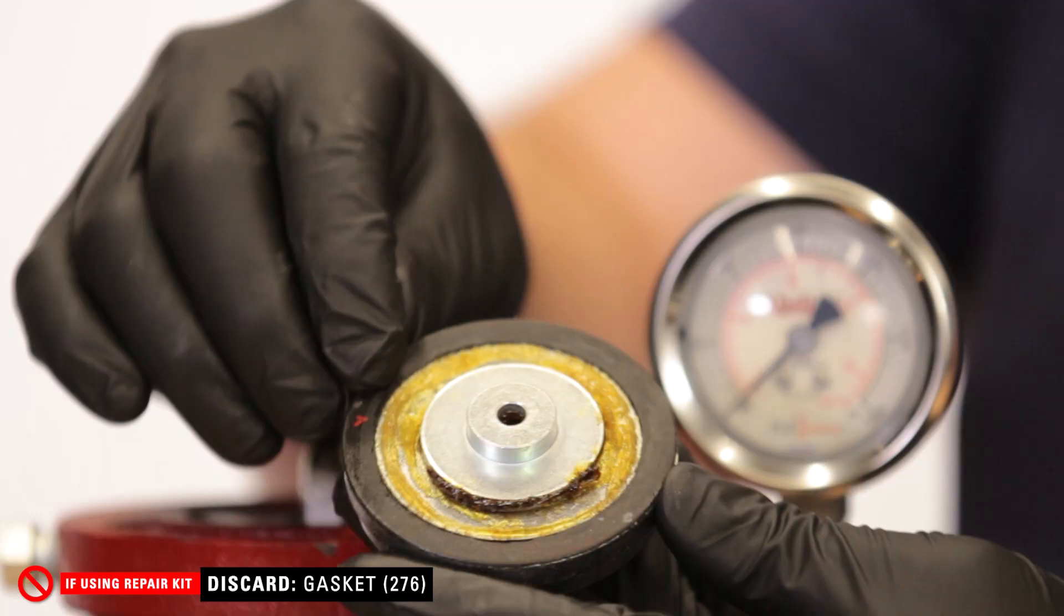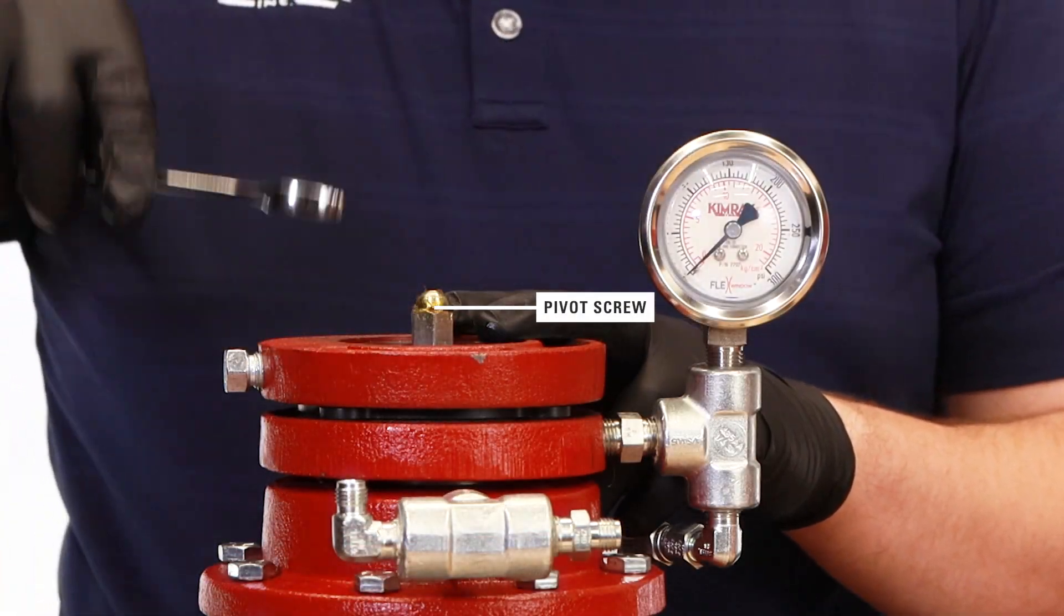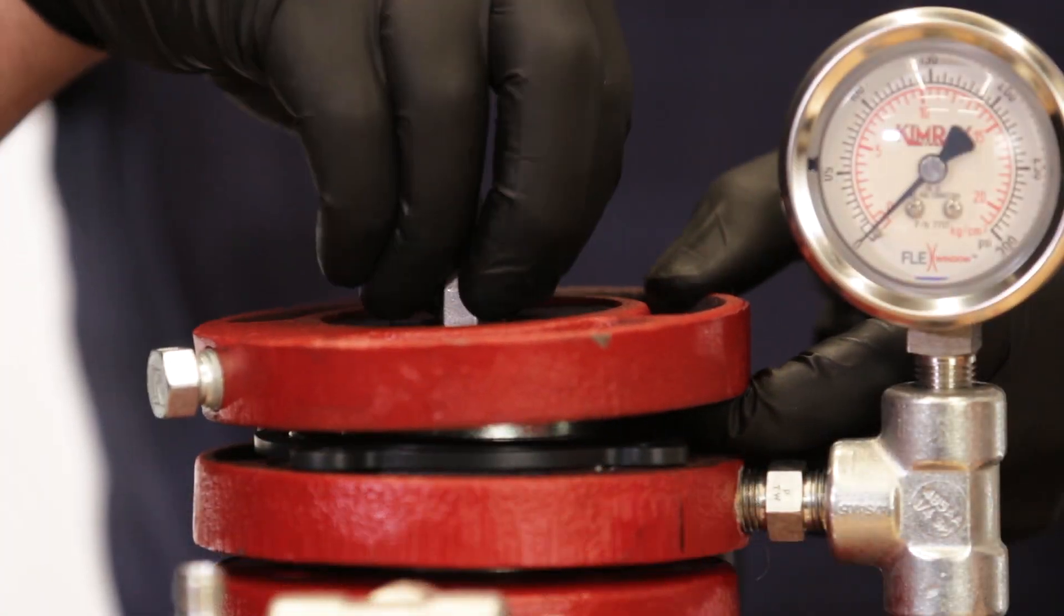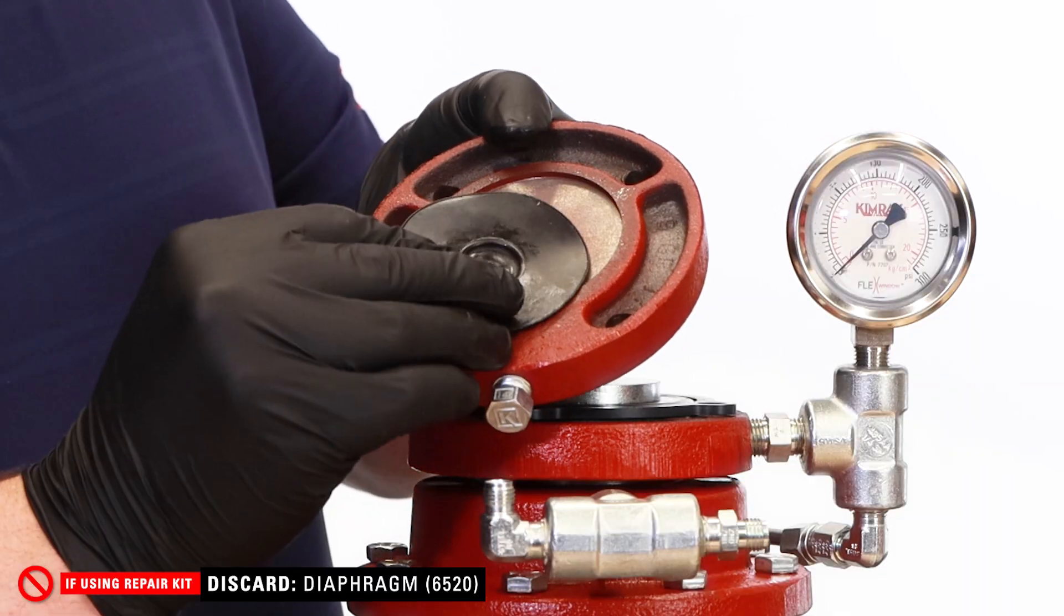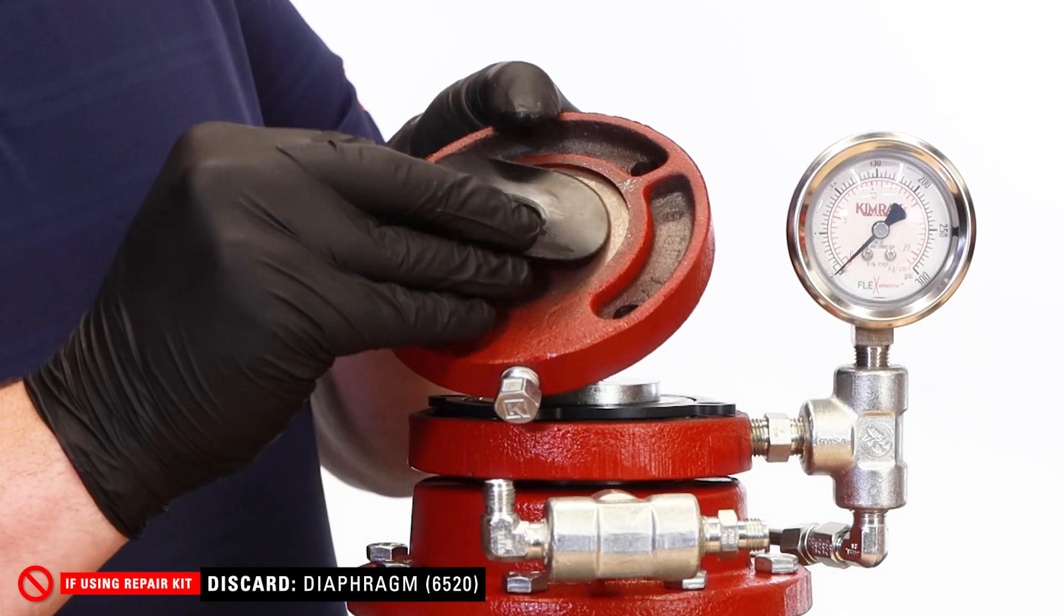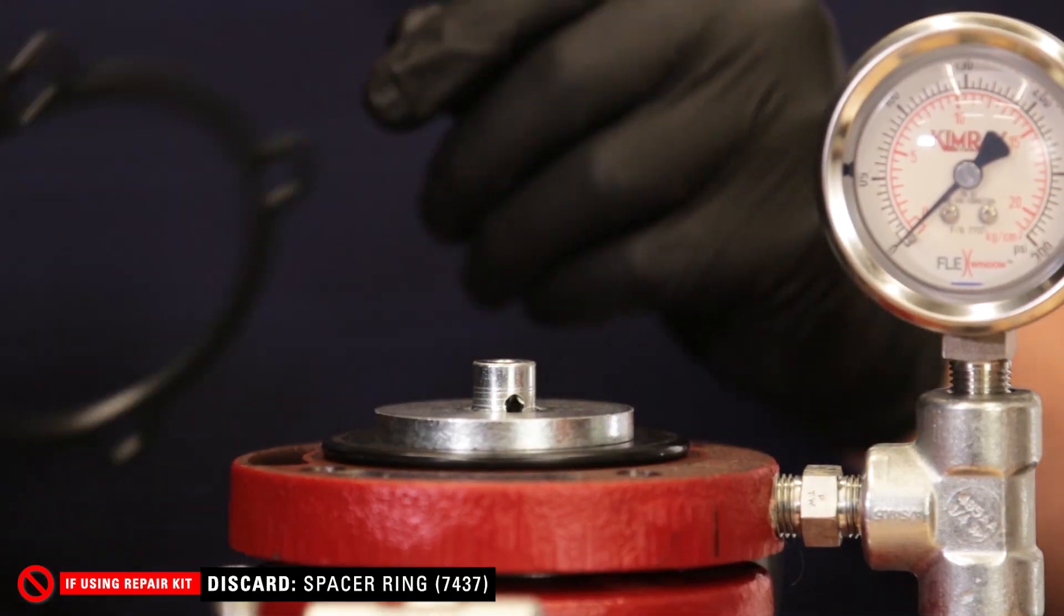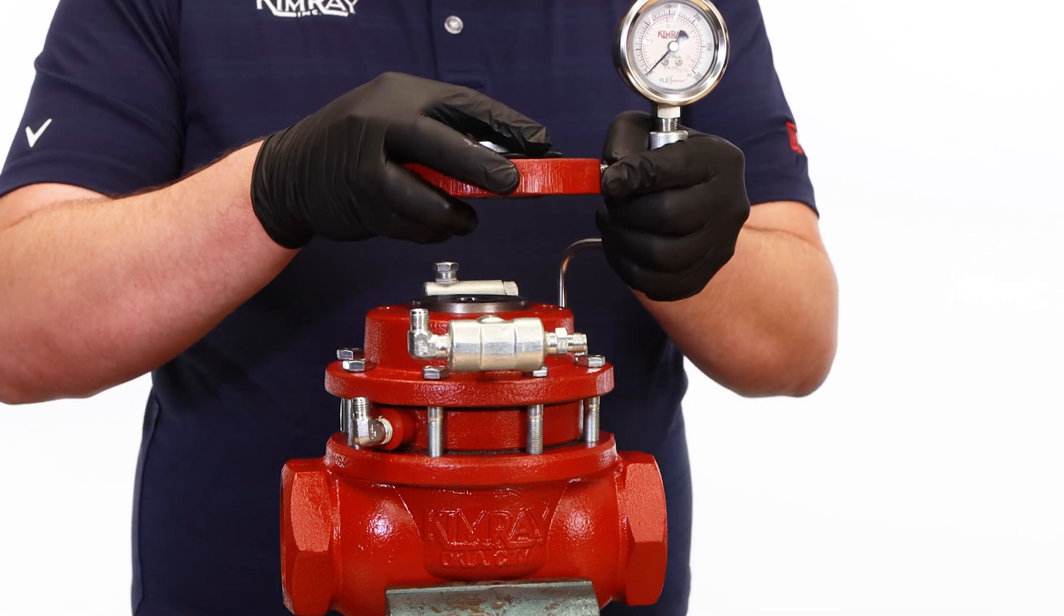Inspect the gasket on the spacer for damage. Remove the pivot screw with a 9/16th wrench. Remove the upper pilot housing and inspect the diaphragm for damage. If it's damaged, it will need to be replaced. Remove the spacer ring. Remove the lower pilot housing along with the pressure gauge and tubing. Set this aside and we will disassemble it in the vise later.